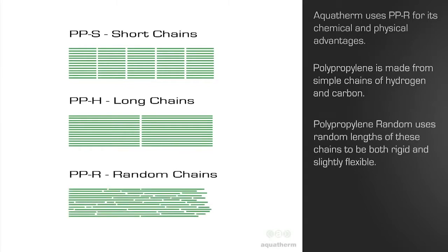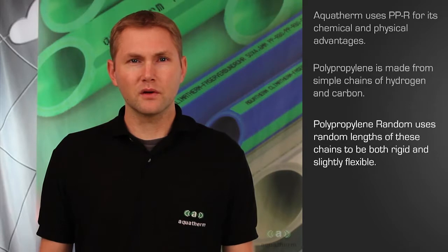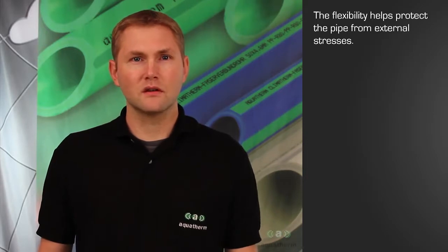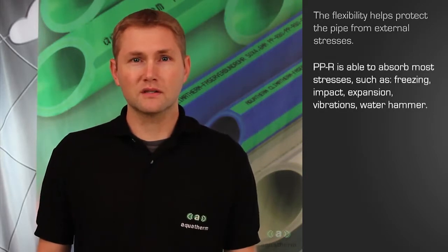Polypropylene random uses a mixture of long chains and short chains to create a material that is both rigid and flexible. The flexibility helps protect the pipe from external damage, such as freezing and impact. It allows the pipe to absorb stress that would otherwise damage other systems, including expansion stresses.